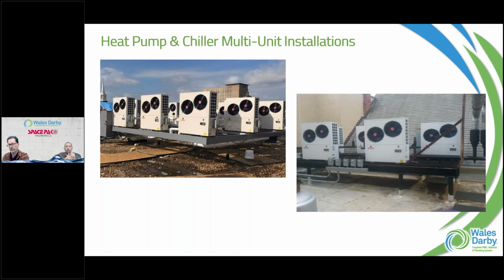We might have 2. So think about the turn down ratio from a 25-ton system that always kicked on full, to now having five 5-ton units. I can modulate down to the lowest modulation of a single outdoor unit, but then bring it all the way up. In this case, this was an inverter system.